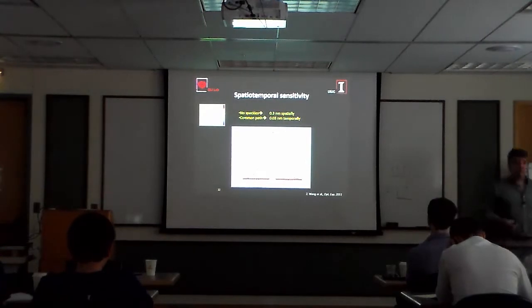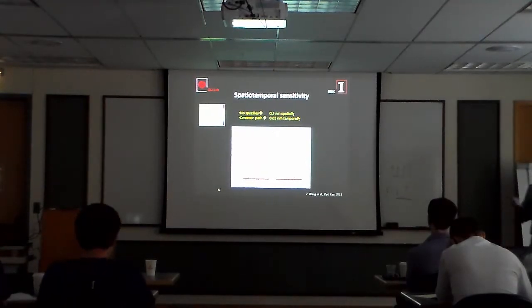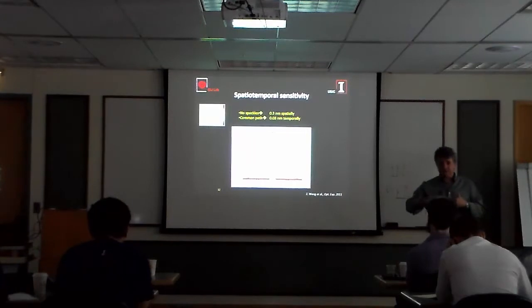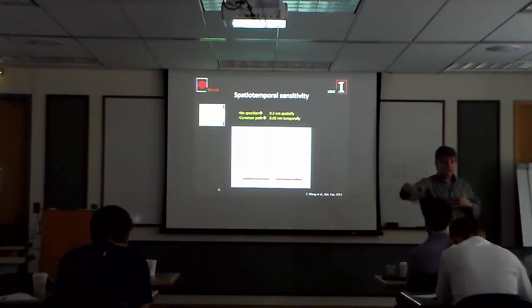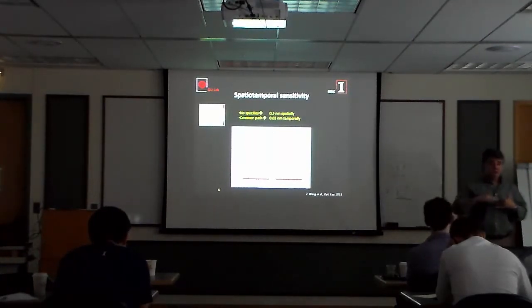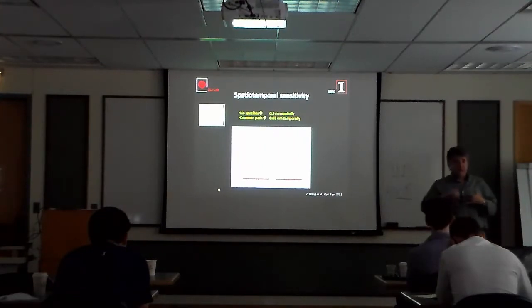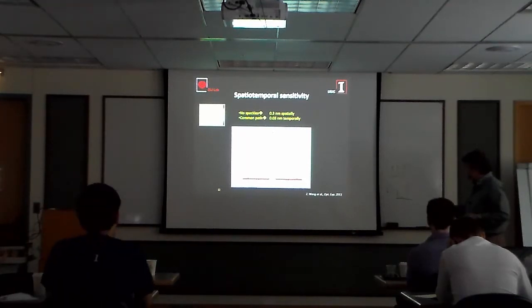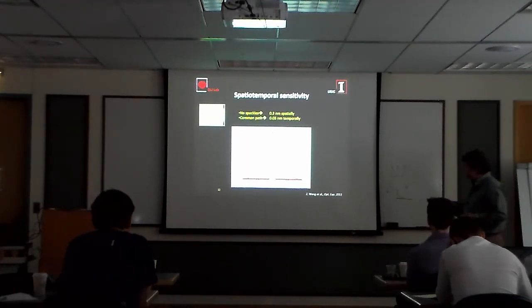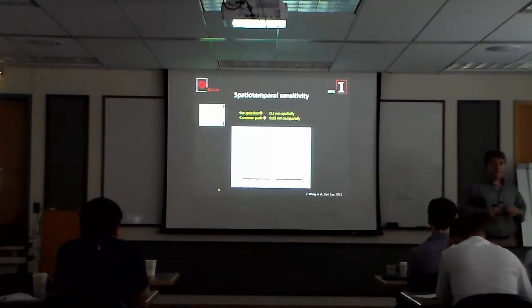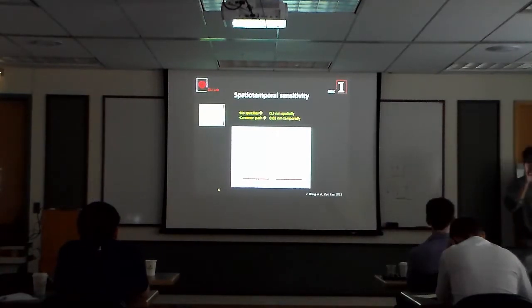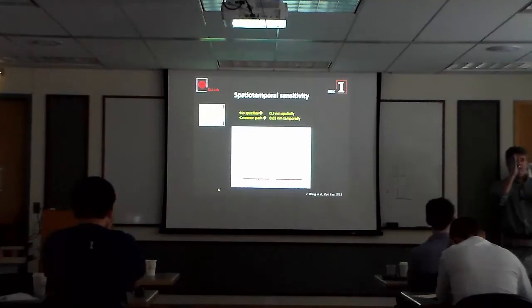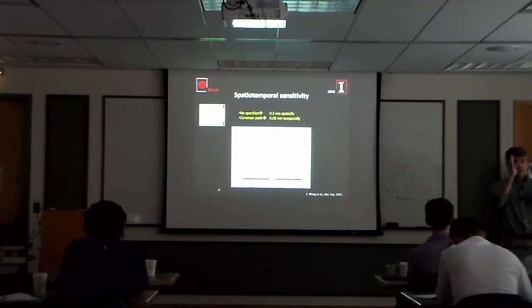What's interesting and surprising to us is that there is another kind of noise in phase imaging, and that is temporal noise. If you measure over and over and over, if nothing moves, you should get a perfect straight line, but in fact you get noise. It turns out that the standard deviation of that, you see the histogram, is actually 10 times narrower. So it's 0.03 nanometer path length. And this is because this is the most common path interferometer you can have. You interfere the light that goes through the cell with the light that's scattered a little bit. It doesn't get any more common path than that.